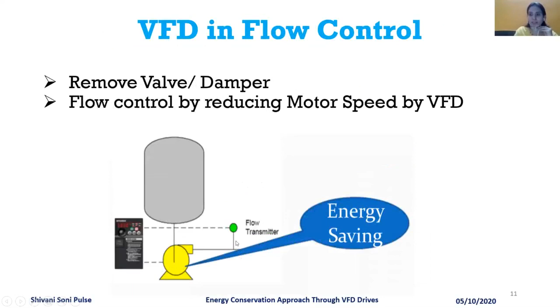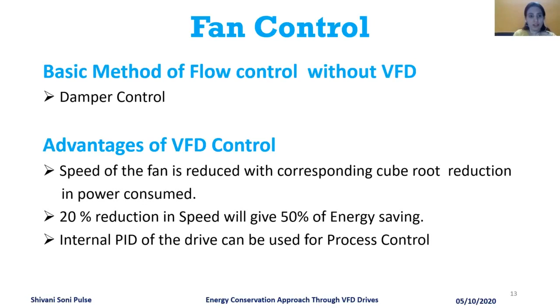Now the potential areas of energy saving in industry are basically fans, pumps, and compressors. In fan control, the conventional method is damper control, where we have to control the damper opening and closing. If we use the VFD instead, a 20% reduction in speed gives 50% energy savings. If we reduce the speed of the motor or fan by 20%, we get 50% energy savings. The same calculation applies to the pump also.